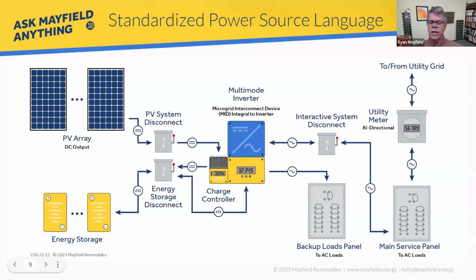And in 706.15—we didn't show all the language—there are multiple options to meet the requirements for that energy storage system disconnect, one of which is integrated into the BESS. So if your energy storage system is listed under 9540, and we're not showing it in this image but showing something external, you can have an integrated disconnect that would meet the code requirement, because you have that disconnect, and in that situation it would be on the DC side. What we're showing here is a DC-coupled system where the PV and the energy storage are coupled together on the DC side. How that exactly happens through the equipment will vary based on the manufacturer.